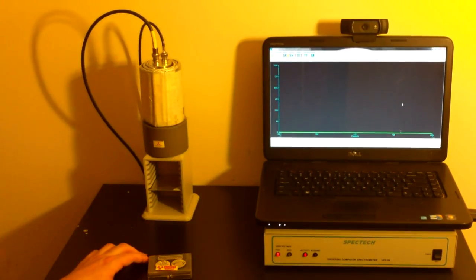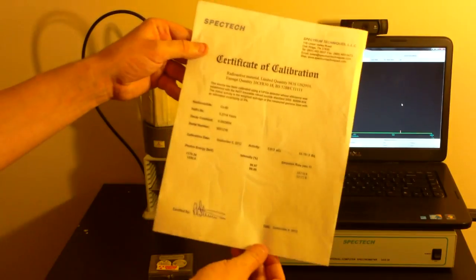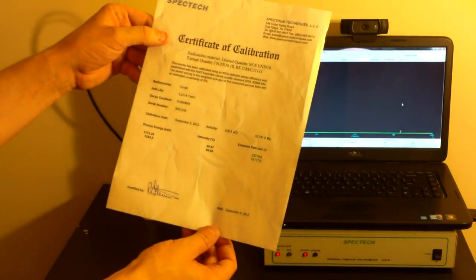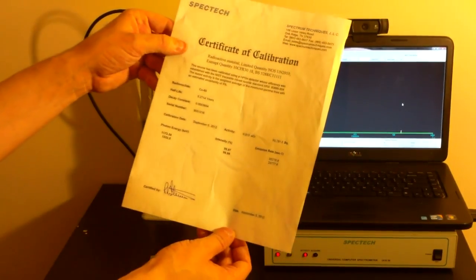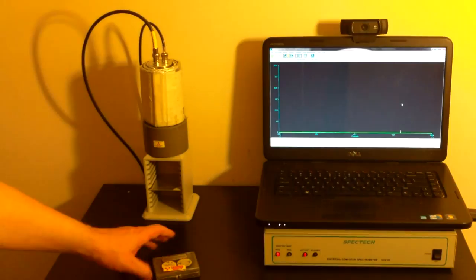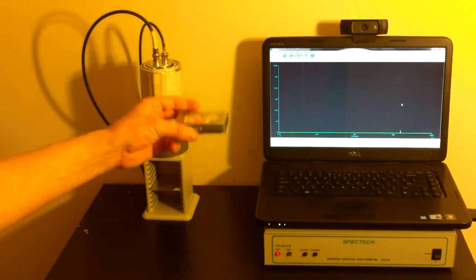decays per second each. The cobalt-60 I have here comes with a calibration piece of paper, a certificate, showing that it has been calibrated, or assayed if you like, to a 95% accuracy based on a NIST traceable source.